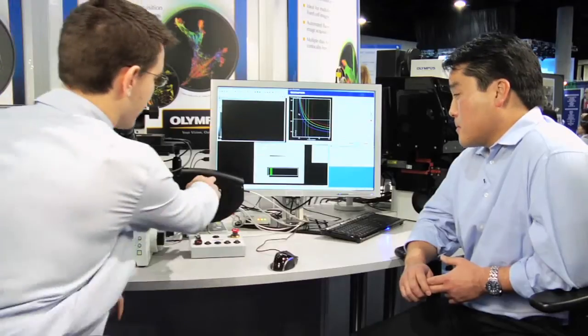Moving further along, each of the lines has its own field stop, which is centerable. So that's a nice feature as well for each of those lines. Something interesting that we have as well, just on the first line, for most systems that are configured, this is the 405 nanometer wavelength, is a lens here.